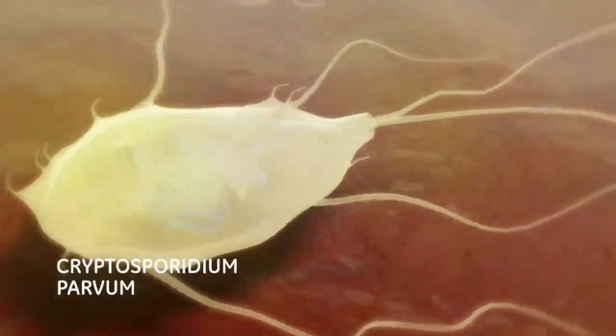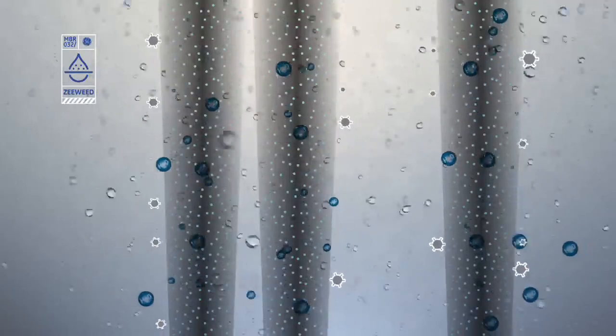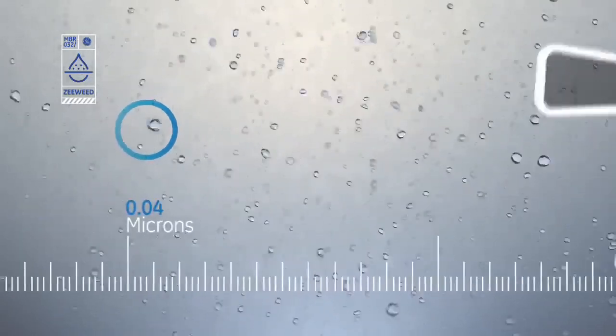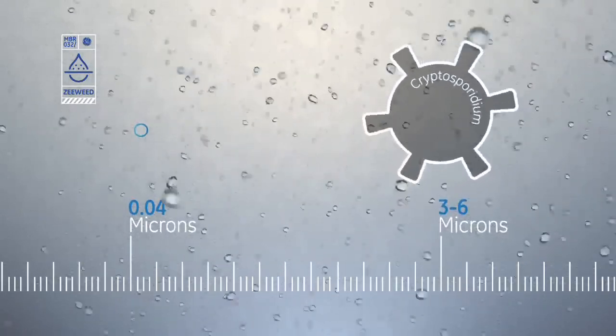Using hollow fibre technology, you're primarily taking out bacteria, microbes, and viruses. Under gentle suction, we are pulling clean water through the membrane. The pore size we're talking about here is 0.04 micron — once you get down to that sort of level, you stop talking about physical size and start talking about molecular size. Parasites like Cryptosporidium and Giardia that you can get in surface water have a size of 3 to 6 micron.